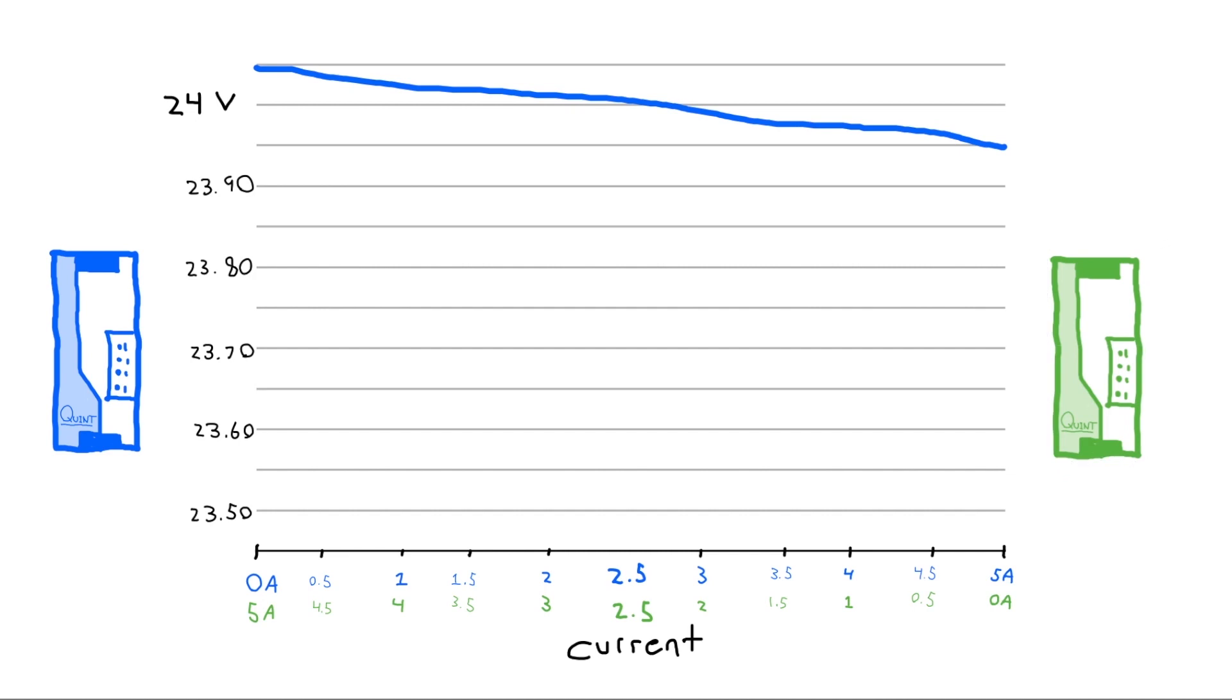When we add another QUINT, we can see how they will cooperate. When the load is at the full 5 amps, the point where their line intersects tells us how much current each power supply will give. If the power supplies have the exact same voltage, they will both give 2.5 amps.